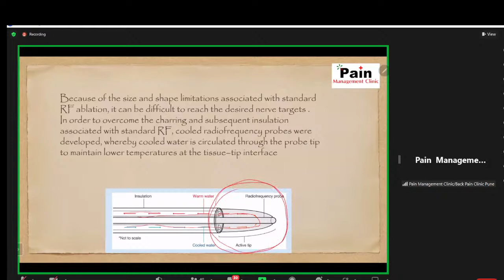So the circulated water serves to carry the heat away from the tissue interface, which will reduce the desiccation and subsequent charring of the adjacent tissue. As such, cooled radio frequency ablation is able to deliver more energy to the surrounding tissue, creating a larger area where the ionic heating can occur. The cooled radio frequency ablation sets a temperature around 60 degrees, and studies have shown that the temperature beyond the tissue interface reaches up to 80 degrees Celsius.